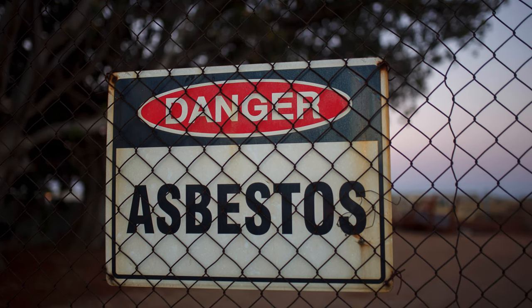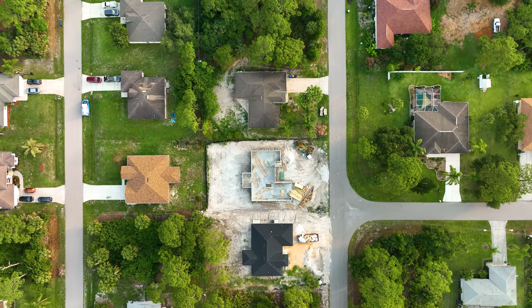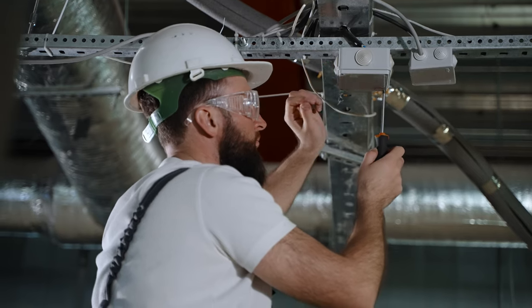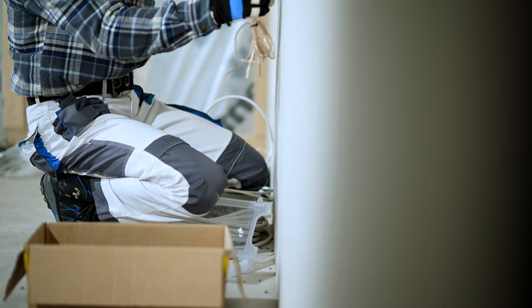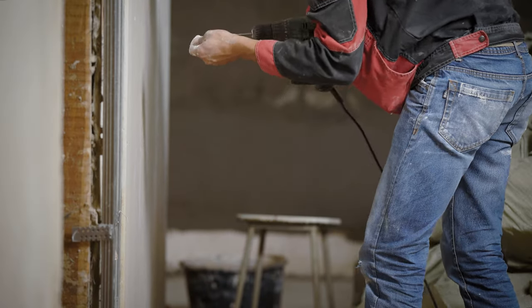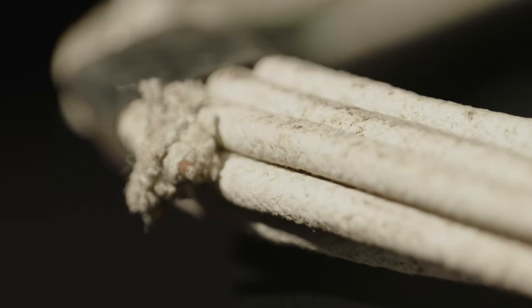There's no known safe level of exposure to asbestos, so always use caution if you're working with something that could be asbestos. A lot of older houses have asbestos insulated wiring, and asbestos is not yet completely banned in the United States. Anyone who's worked with or near the electrical wiring or components in older buildings may have been exposed to asbestos. The people most at risk include electricians, but anyone remodeling an older home should take caution and use proper protective equipment — especially if you're planning on updating light fixtures or older wiring insulation, or if you plan on opening or moving drywall, plaster, or older ceiling tiles, all of which have been manufactured with asbestos in the past. Remember to keep an eye out for fuzzy or furry, often white fibers amid the braided insulation around the electrical wiring — that's asbestos, and it's what you want to watch out for.